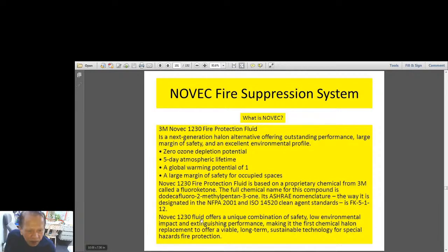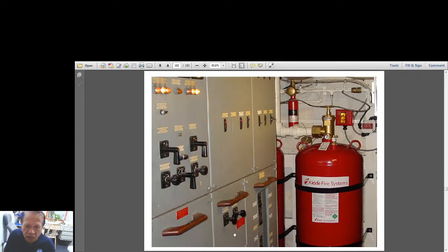FK-5-1-12. Novec 1230 fluid offers a unique combination of safety, low environmental impact, and extinguishing performance, making it the first chemical halon replacement to offer viable, long-term, sustainable technology for special hazards fire protection. So now, as a replacement to the halon, we have the FM200 and now the Novec. Okay. And here is a sample of installation of the Novec. The brand is Kidde Fire System. So you would see the agent tank and the piping here, okay, supplying to the switchgear.